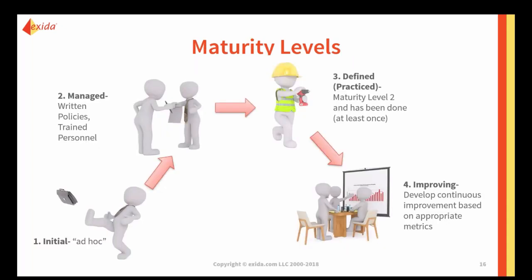Depending on how familiar you are with the different IEC 62443 standards, you may have heard the term security levels before. A security level talks more about the level of security achieved for a specific device or a specific zone. Whereas a maturity level talks more about how well-defined processes are and how repeatable it is to achieve that security. And so there are 4 maturity levels defined.